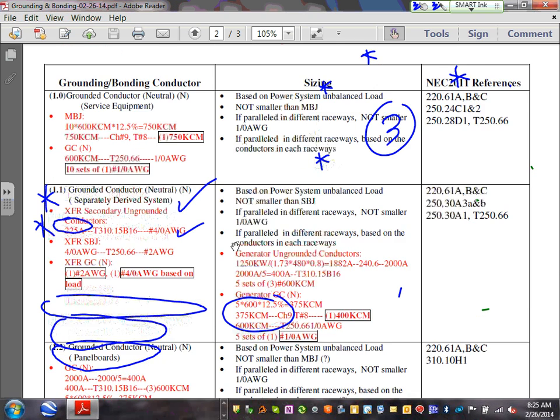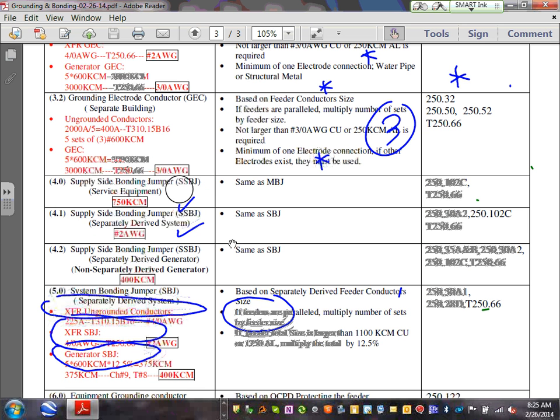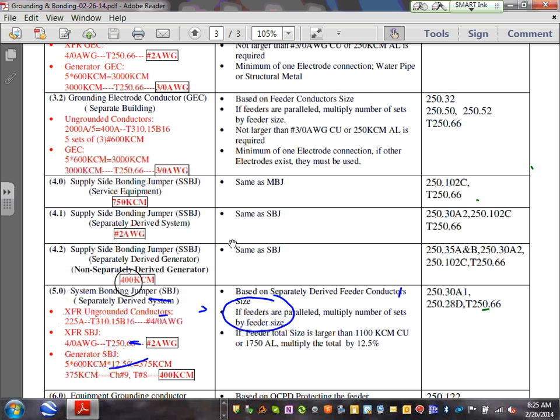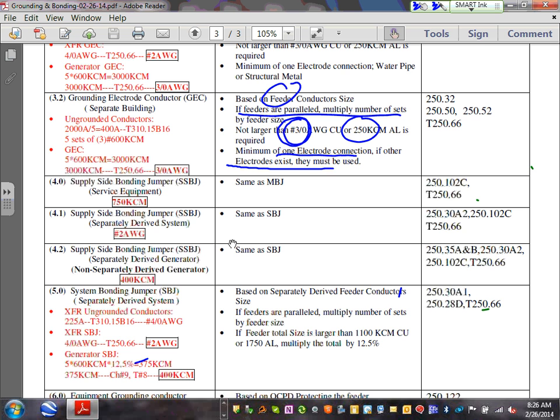The grounding electrode conductor, Table 250.66. Let's go to 3.2. So if you guys go to 3.2 right in here, here's my 3.2. 3.2, gentlemen, has a size exactly like any equipment grounding conductor based on the feeders. For the second building, we size it based on the feeders. Can you guys see that? Based on the feeders, you have to multiply by the sets if you have them. You don't have to go larger than these two numbers. And you have to have at least minimum one grounding electrode conductor, but if others exist, you have to bond to them.